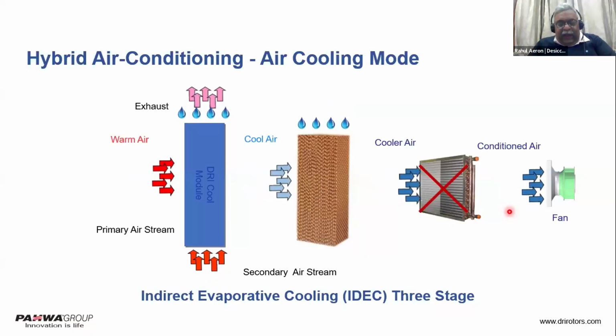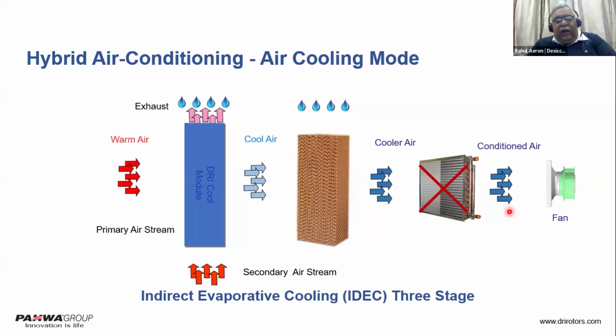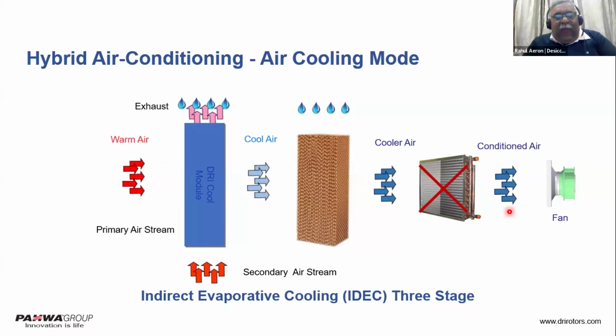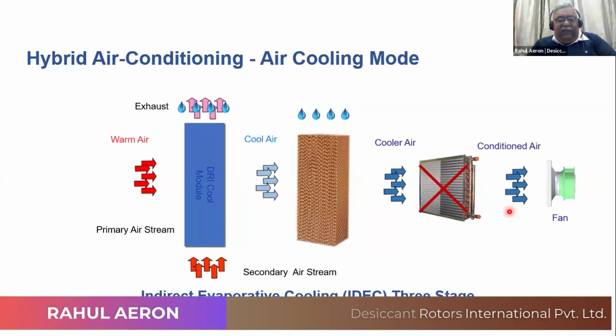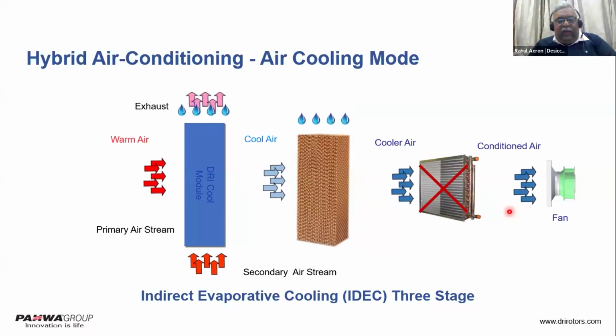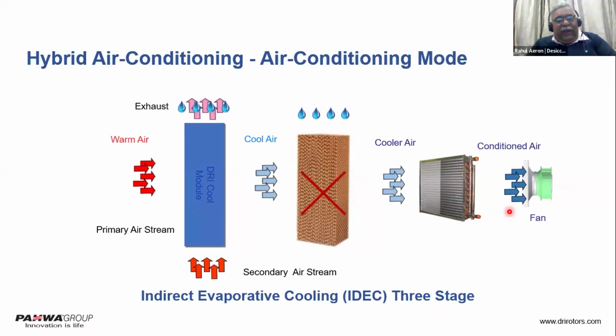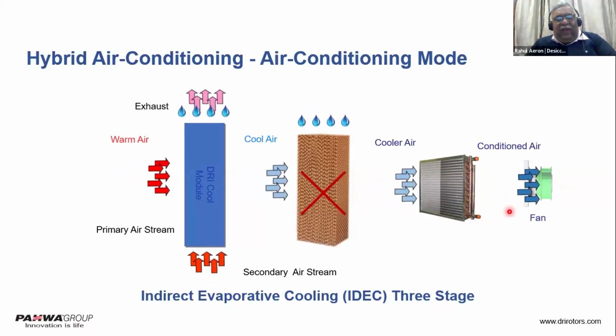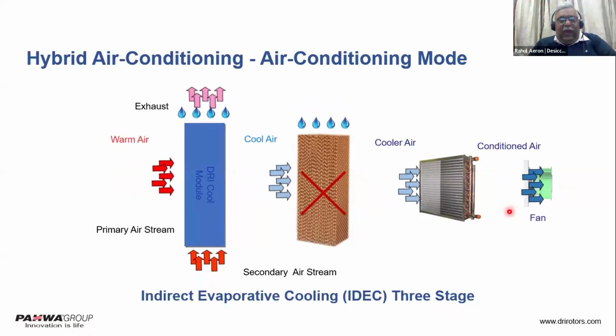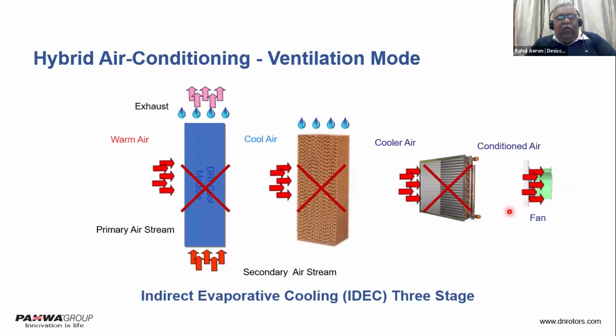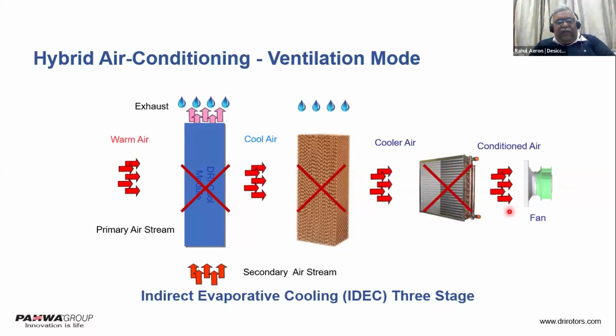Now, as I was mentioning earlier, we can always club this technology with a refrigeration-based or compressor-based technology. So this is what I wanted to highlight. We can design a hybrid air conditioning system. Anybody can design a hybrid air conditioning system. So when it's hot and dry outside, so when it's summer, as we call it in the northern part of India, then you run this system only in air cooling mode. You run it in two-stage evaporative cooling mode. When you have high humidity, then you switch off the second stage, where we are adding the moisture, and you start your mechanical cooling. So that's called hybrid air conditioning mode. And then when you have winters, you simply ventilate the space. You run neither the water nor the refrigerants. So that's how you can have a simple free cooling mode, as we call it, in this kind of system.